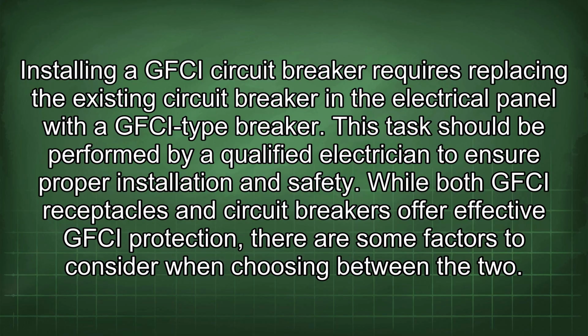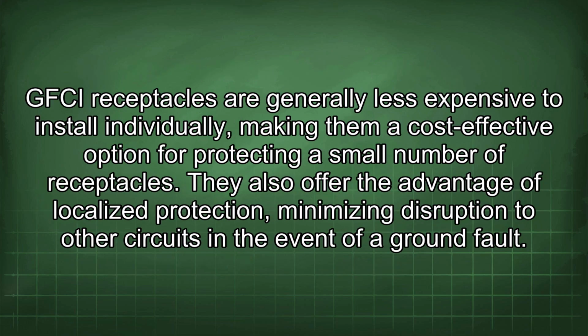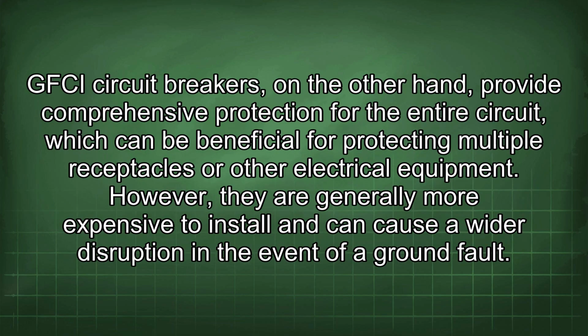While both GFCI receptacles and circuit breakers offer effective GFCI protection, there are some factors to consider when choosing between the two. GFCI receptacles are generally less expensive to install individually, making them a cost-effective option for protecting a small number of receptacles. They also offer the advantage of localized protection, minimizing disruption to other circuits in the event of a ground fault. GFCI circuit breakers, on the other hand, provide comprehensive protection for the entire circuit, which can be beneficial for protecting multiple receptacles or other electrical equipment.